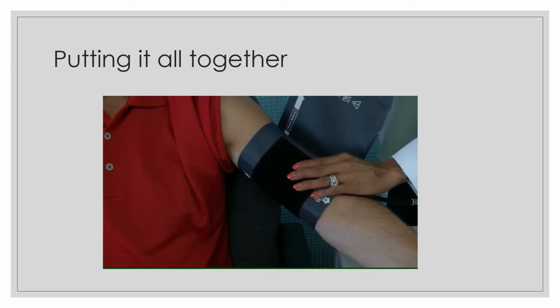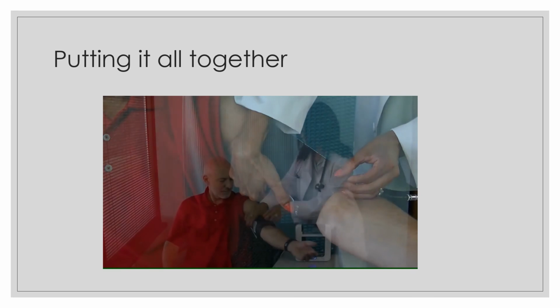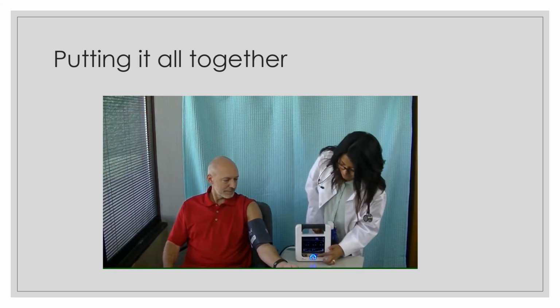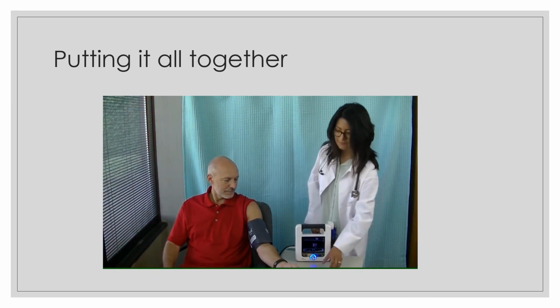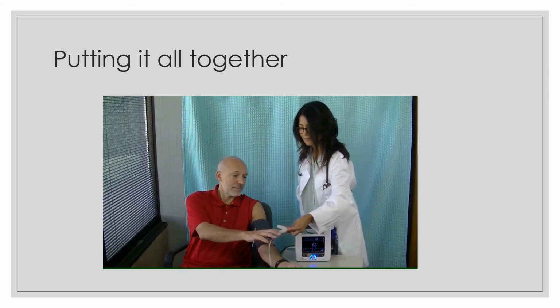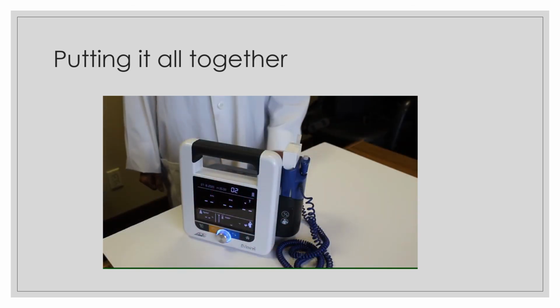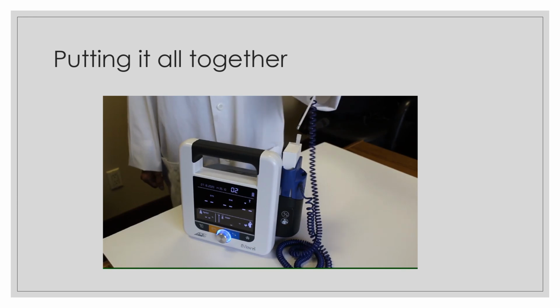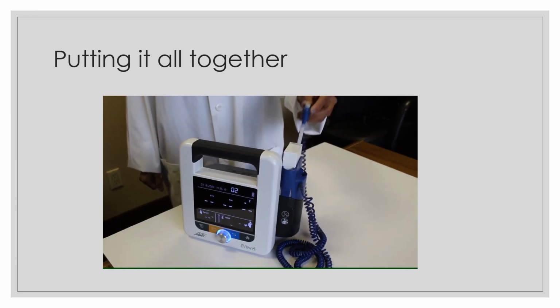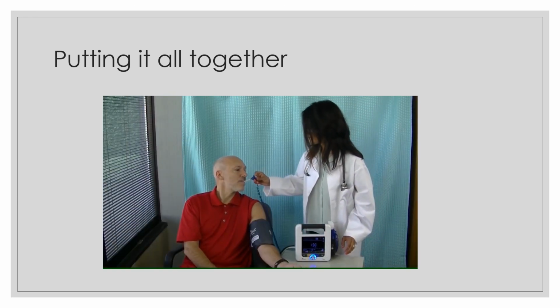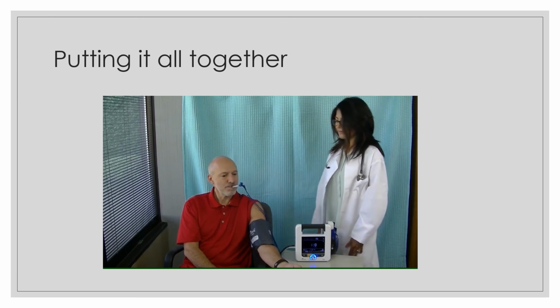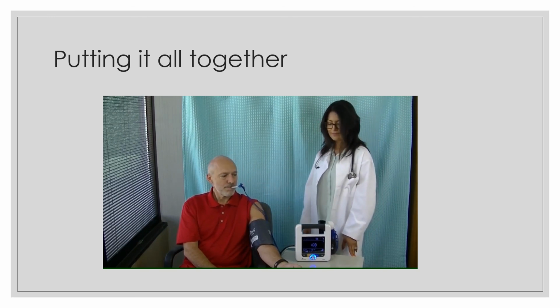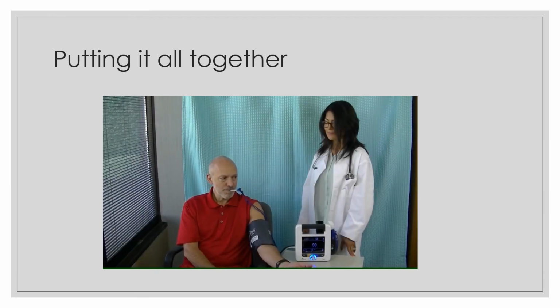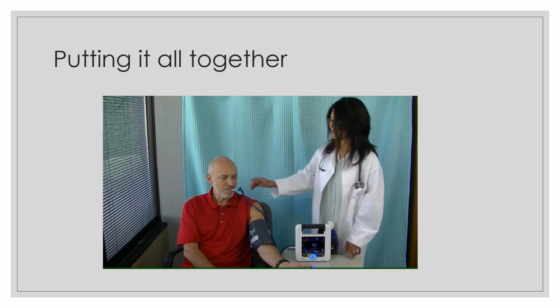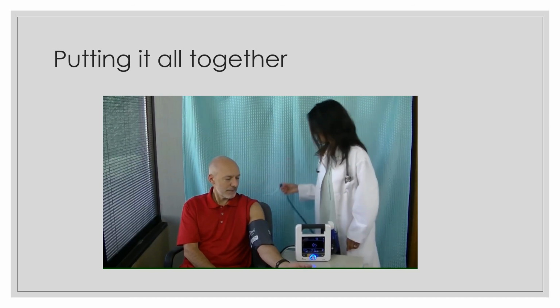Begin the measurements by properly applying the cuff to the patient's arm. With the cuff in place, press the Stop-Start button. Place the SpO2 sensor on the hand opposite the blood pressure cuff. Next, remove the temperature probe, put on a probe cover, and place it in the patient's sublingual pocket. Each measurement will display when complete. All should be ready within about 30 seconds. Measurements can be taken in any order, but this sequence is optimized so the longest, blood pressure, is started first.